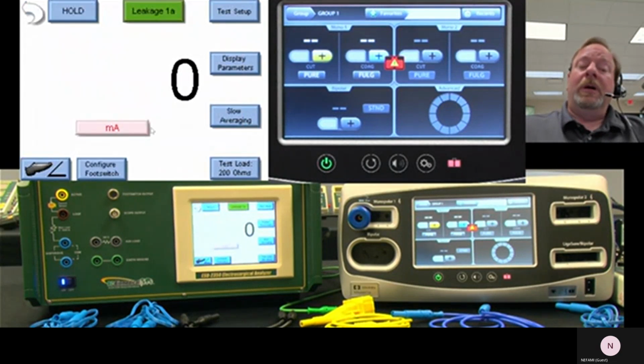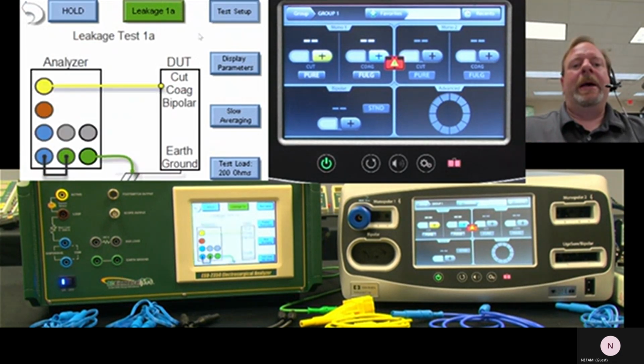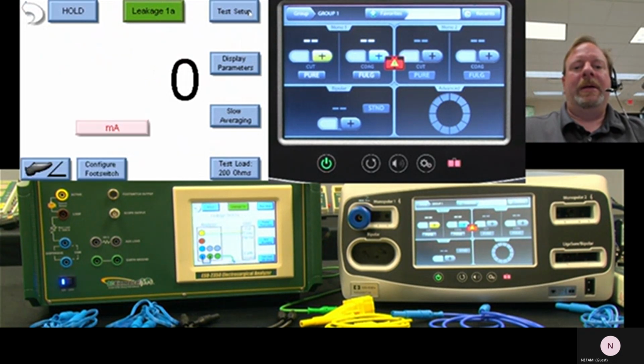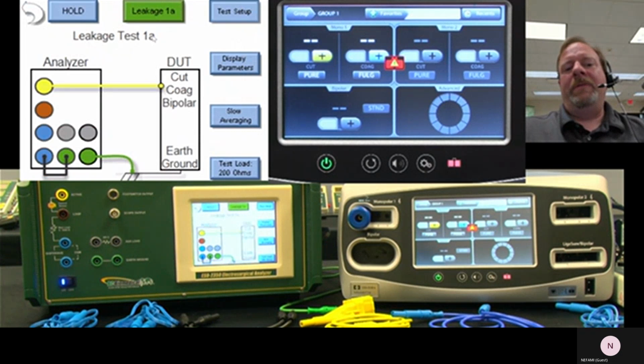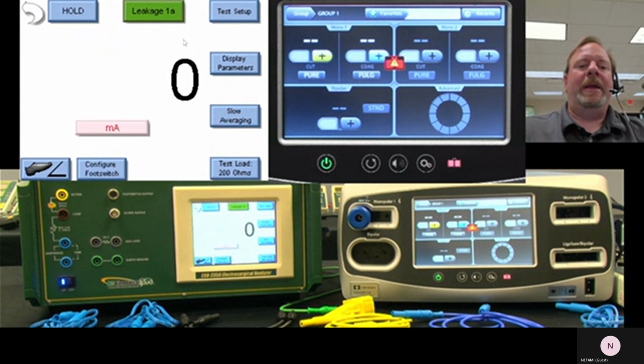The other thing that we would do on a routine day-to-day basis, just manual testing, is leakage. And so we'll see the screen is the same interface, but we change the button to green just to indicate you're doing earth leakage testing. And also our setup pictures change. It shows us how to do connections for all of these testing. Now we've given these names, leakage 1A, 1B, 2, and 3. Those match the ESU 2400 nomenclature. So if you're used to that terminology, you'll see the same thing here. Again, the connections just have to be done manually.